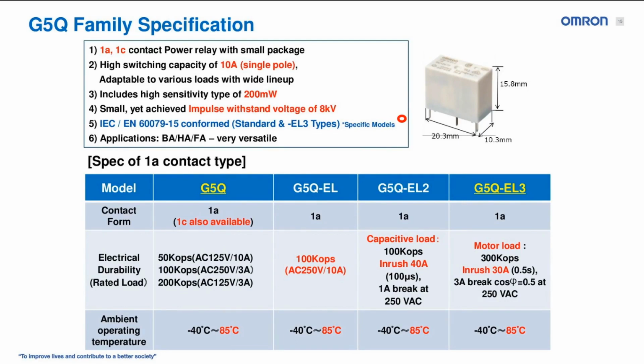Now down here, again, I've highlighted in yellow what products are available for this explosion rating, anti-explosion rating. The G5Q standard is one form A or transfer contact one form C, so switching between modes. We have high endurance for the different ratings in the standard product. And then let's look over here on the right. This is for those motor load applications, the G5Q EL3. So it only comes in one form A open closed relay, but it offers a high 300,000 operation motor load rating for a 30 amp inrush with a 3 amp break at 250 VAC. So for those motor applications around 10 amps, this is the product we look for.